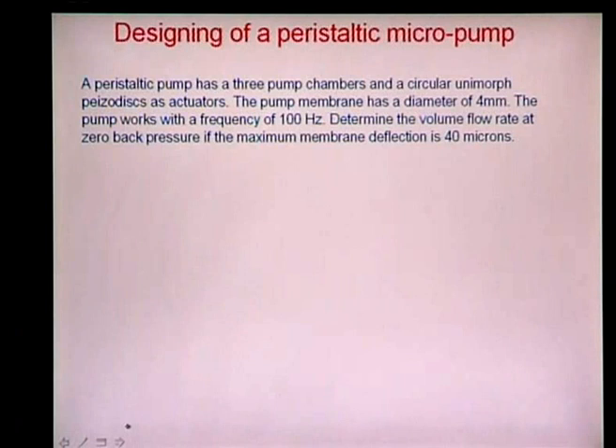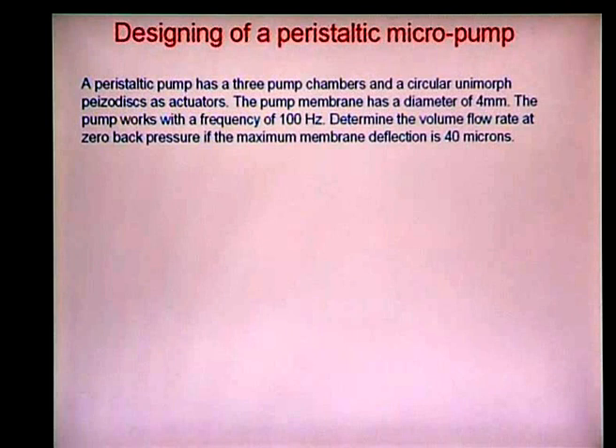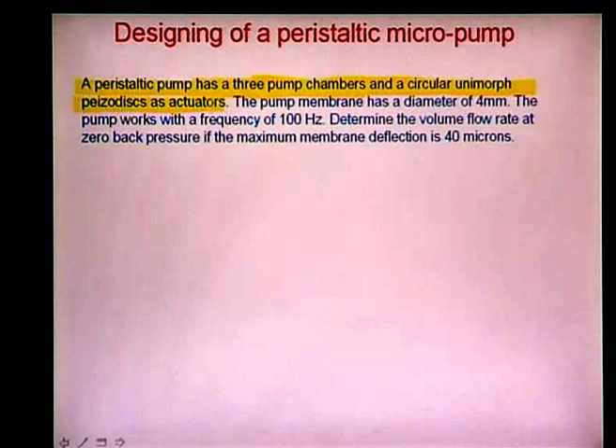Today we will discuss a design problem on how such mechanical pumps can be designed and developed. In this example, there is a peristaltic pump with three pump chambers and a circular uniform unimorph piezo disk as actuator. The pump membrane has a diameter of about 4 mm.